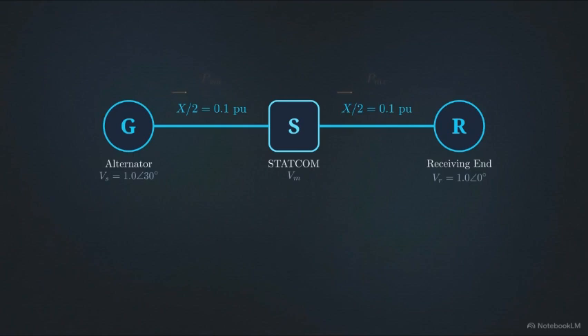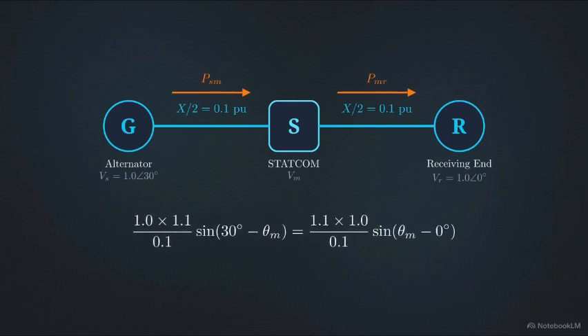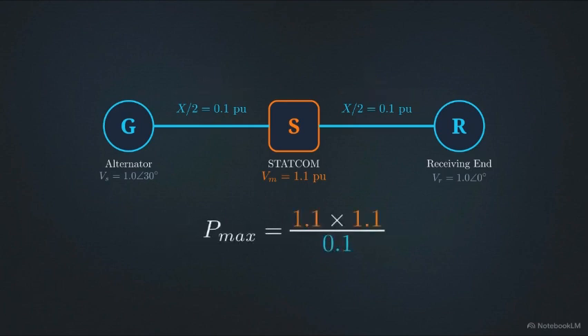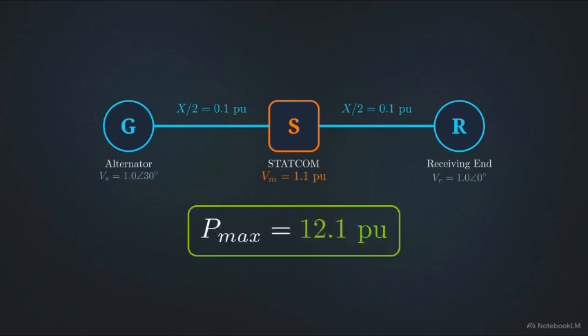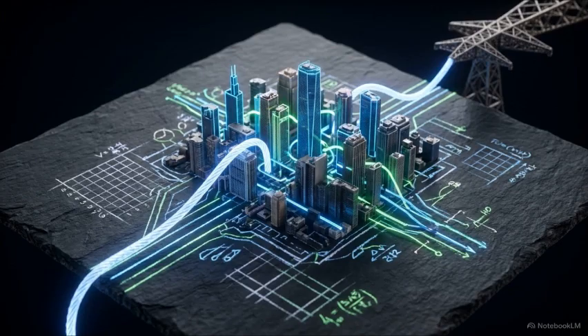By actively clamping the voltage at the precise center point, the STATCOM node physically splits that total reactance exactly in half. This equation maps the required physical balance. For the system to hold, the power transferred from the alternator out to this new midpoint must perfectly equal the power moving from the midpoint to the receiving end. By artificially holding that midpoint voltage steady at 1.1 per unit, the STATCOM shores up the sagging power potential over the long span. Combining that boosted midpoint voltage with the halved line reactance calculates out to a significant increase in the stability limit, reaching 12.1 per unit. By mathematically cutting the distance in half, grid engineers can effectively double the grid's power ceiling without laying a single mile of new wire.